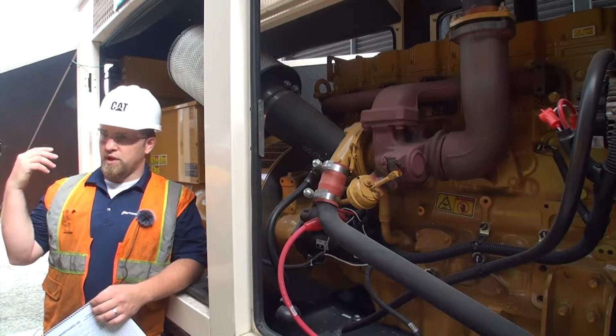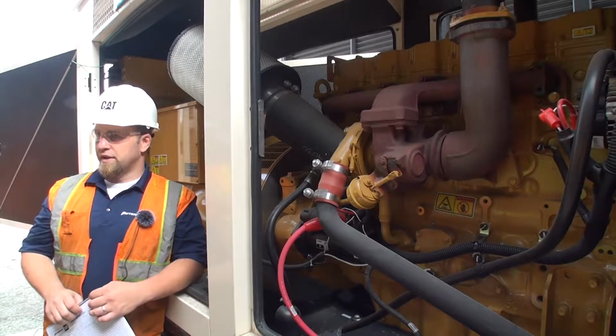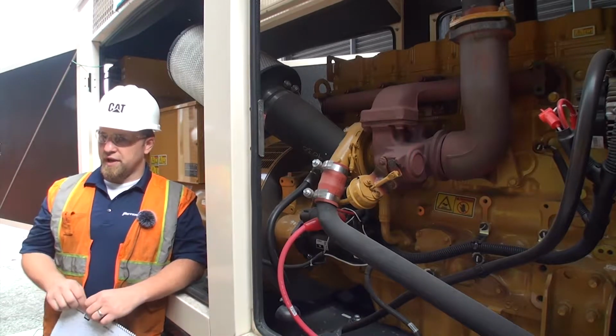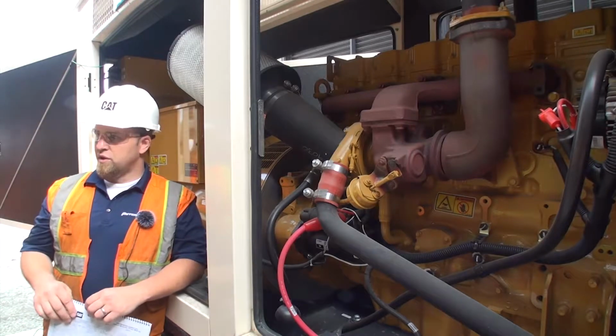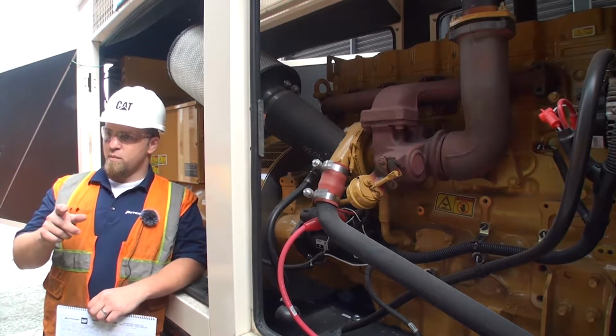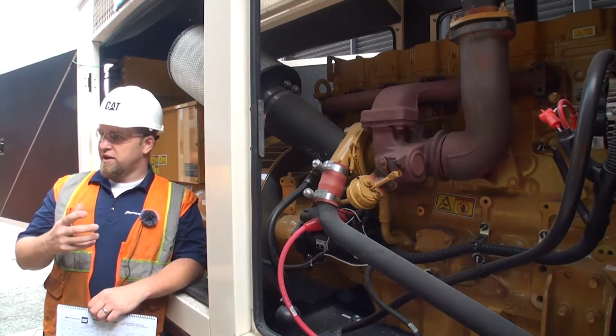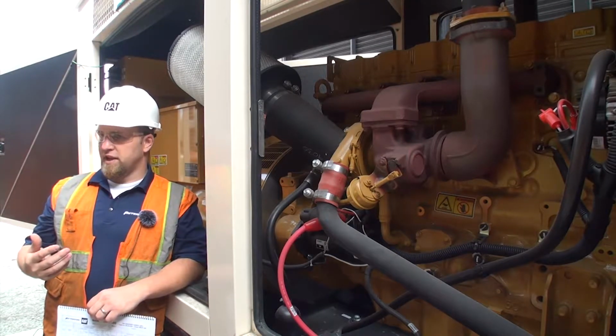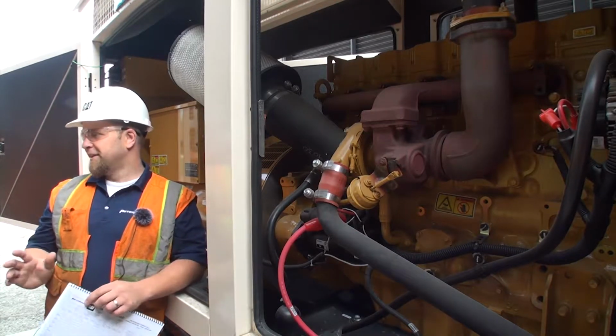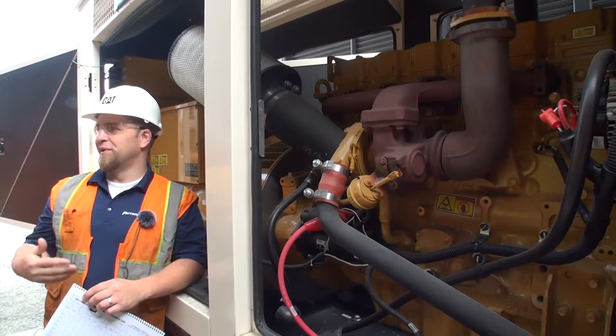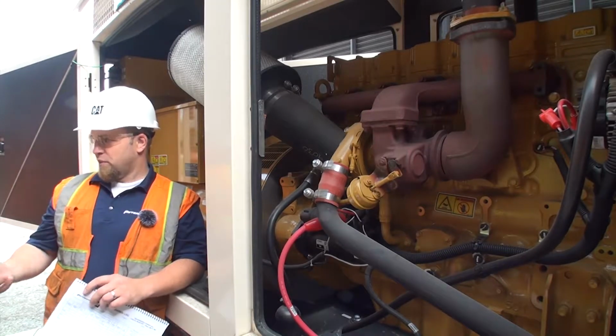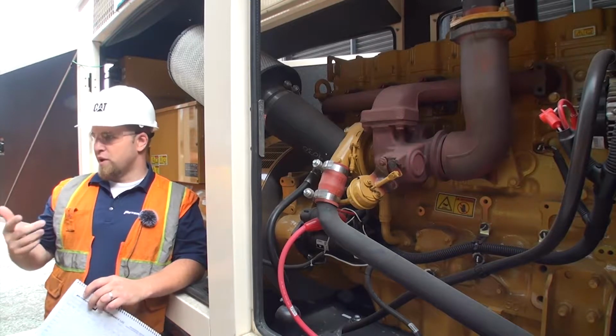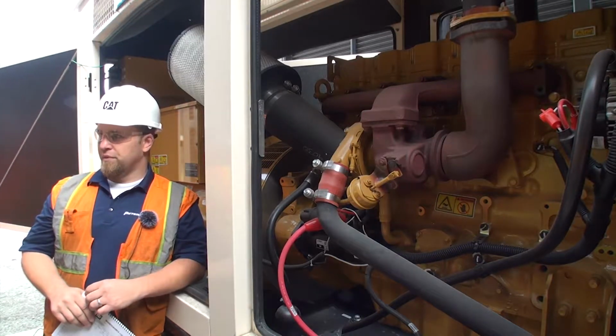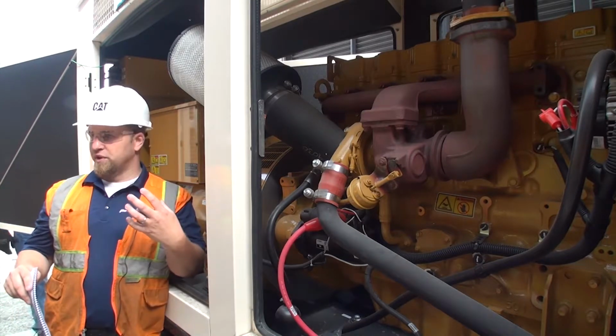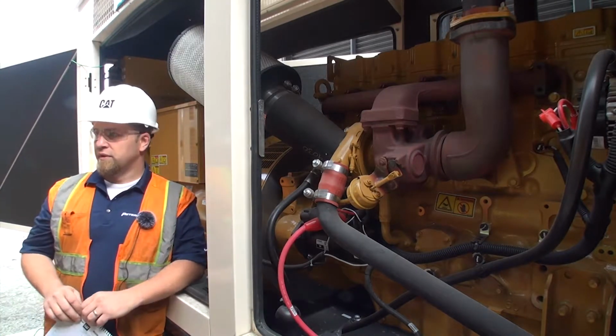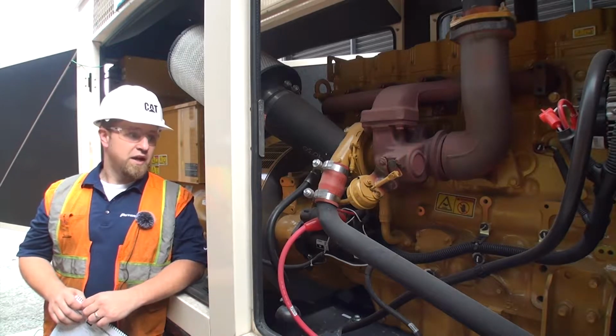Playing with it, playing with the panel, running it, getting used to it, the better off you're going to be. With the transfer switch and everything else, you're probably about a year of warranty or less, so the more transfers you do and the more familiar everyone is with the work here, the better off you'll be. If they say a fire panel alarm happened because you did a building transfer, that shouldn't be the case. You should be able to do a building transfer monthly, since that's what code requires, without it causing fire panel alarms. There are settings for everybody, so you should be able to set a time delay so the system knows this is a building transfer and it's okay once a month. Just getting ahead of it now is the best thing I can tell you guys.